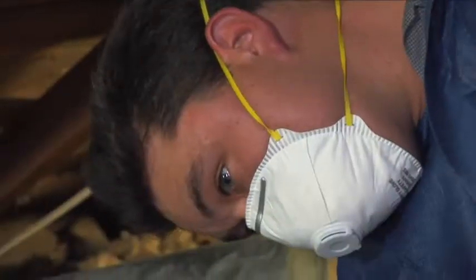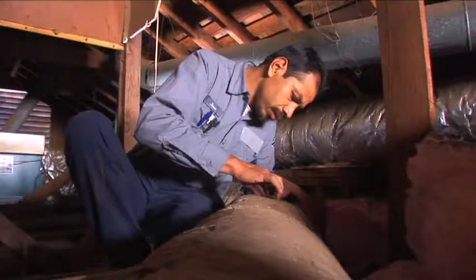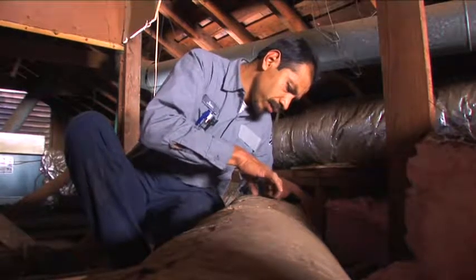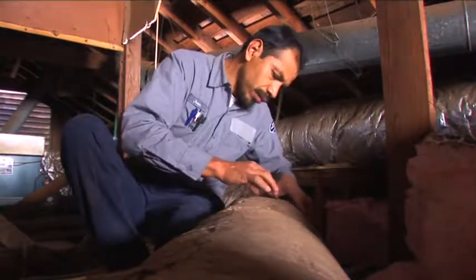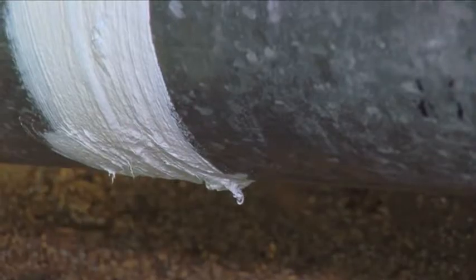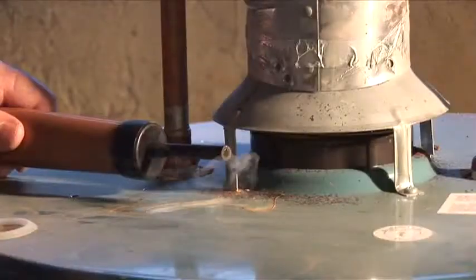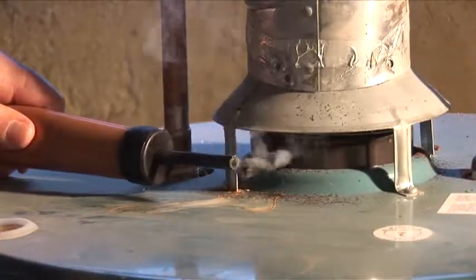Sealing duct leaks always has positive benefits, but you have to be careful because there's a high potential to change internal pressures. We've seen many cases where a contractor had good intentions but wasn't well trained and actually caused dangerous safety issues. For example, sealing leaks can inadvertently cause negative pressure that backdrafts a gas appliance.